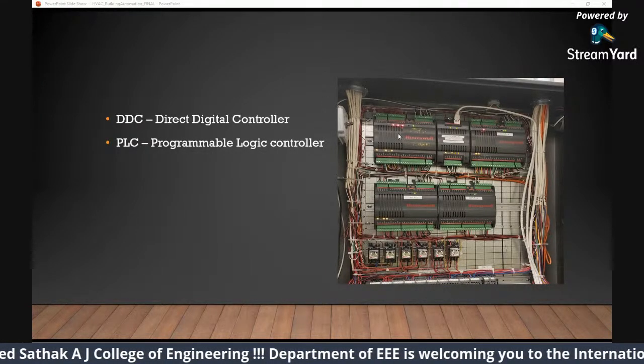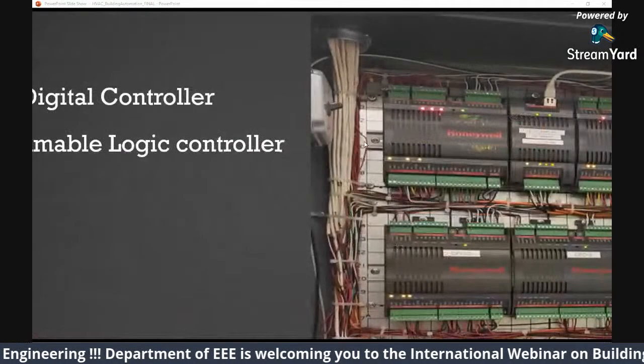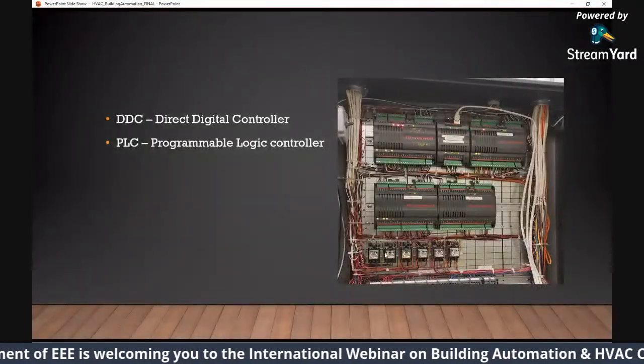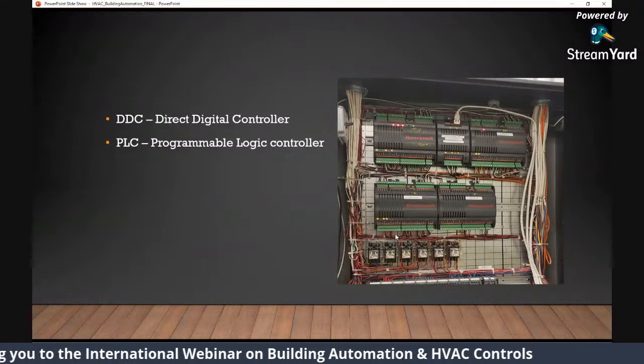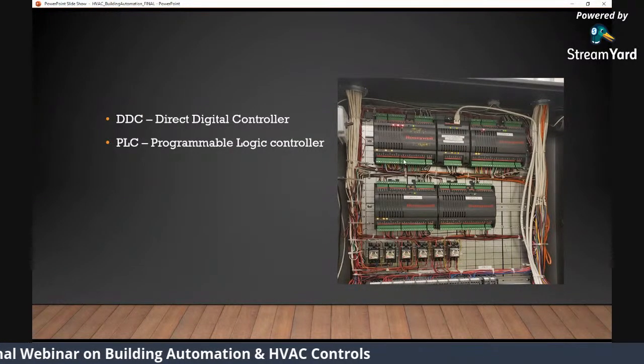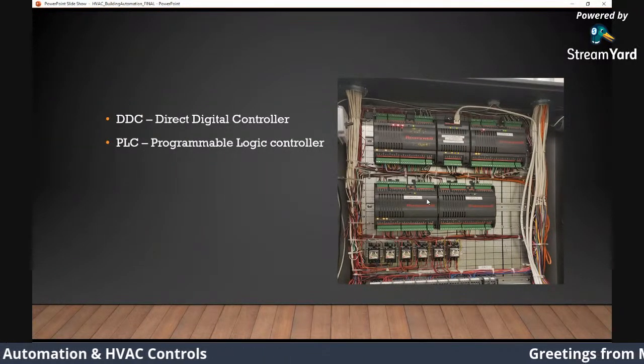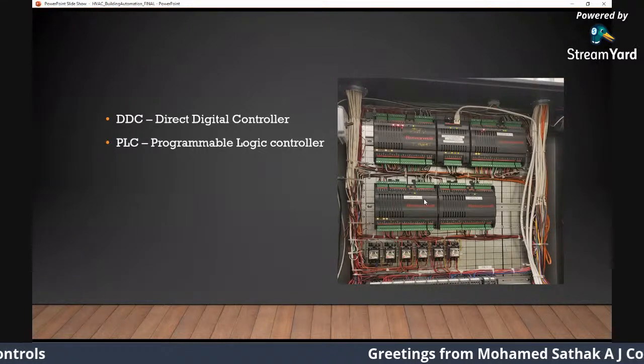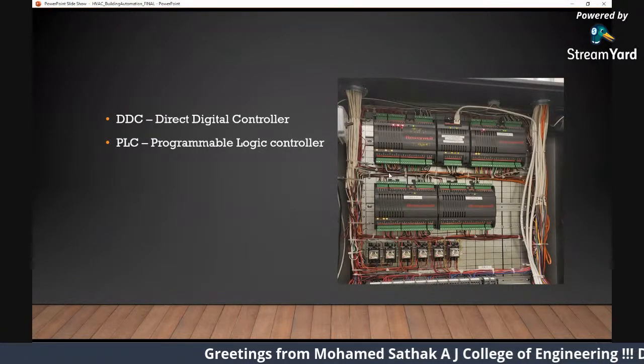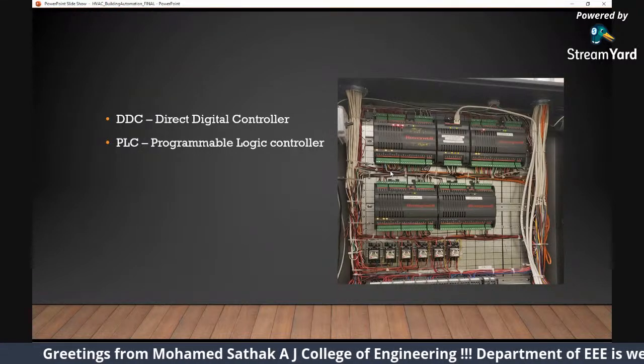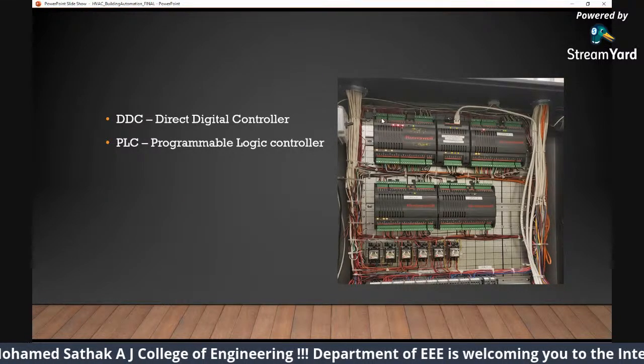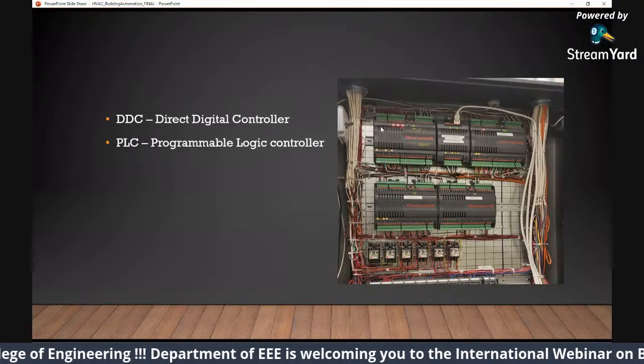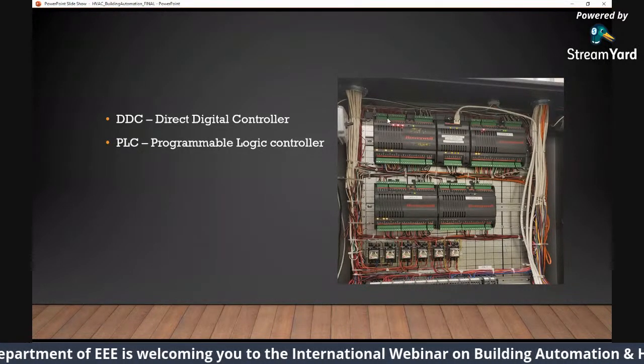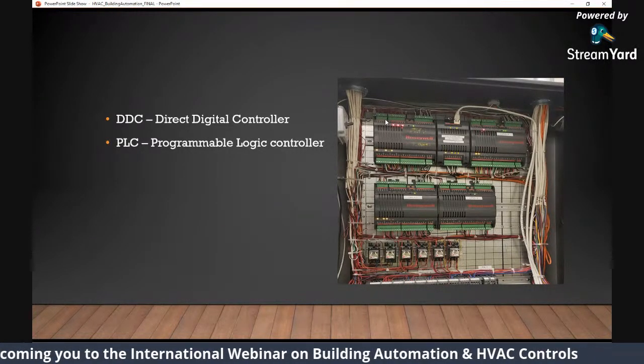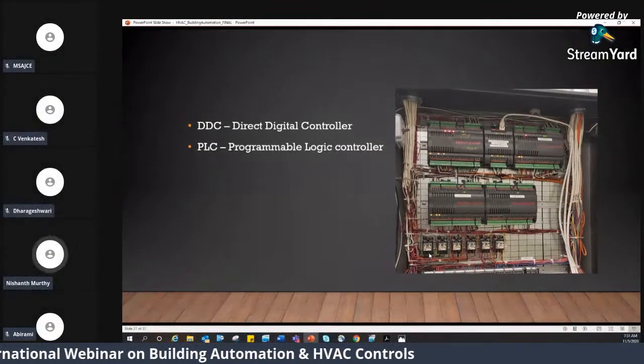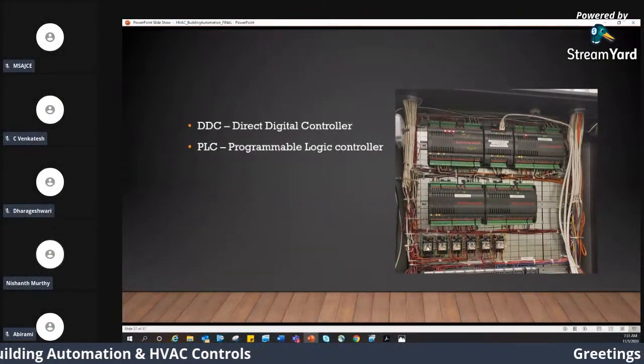So this is one example. If you scroll down, you can see those small cubicle things at the bottom of the panel, those are your relays. Again, the sensors will be in the field. It will be on the AHU, it will be in your rooms and everything. Relays will be mounted in the panel. This is your panel. All your wiring which goes to the controller, or your wiring from your temperature sensor, pressure sensor and everything, those are your inputs, so the bottom ones are your inputs. The ones above the controller are outputs, which again go to the field, like actuators, VFDs and everything. The bottom ones are your relays, which turn on your fans and pumps and everything.